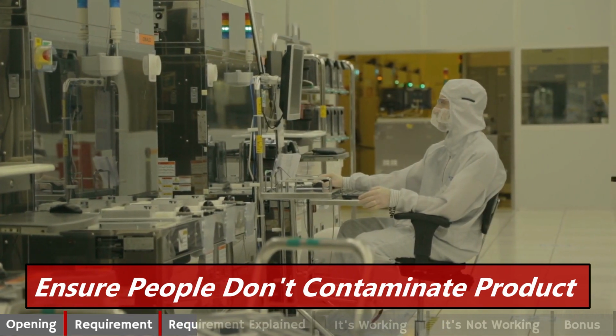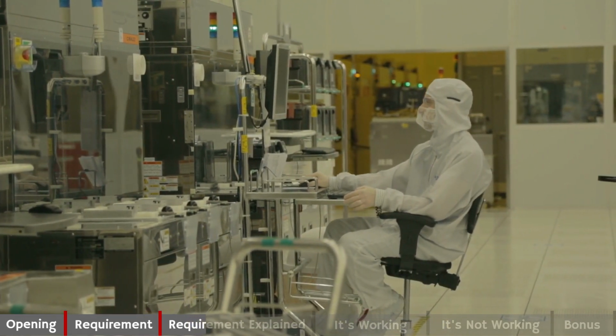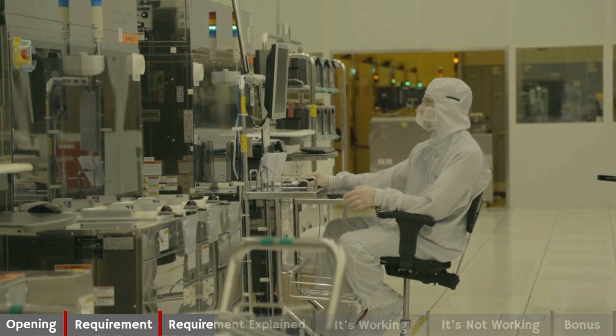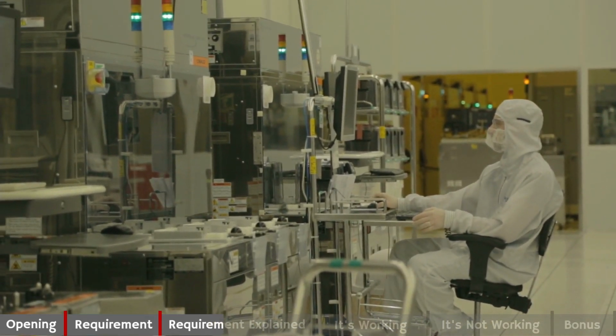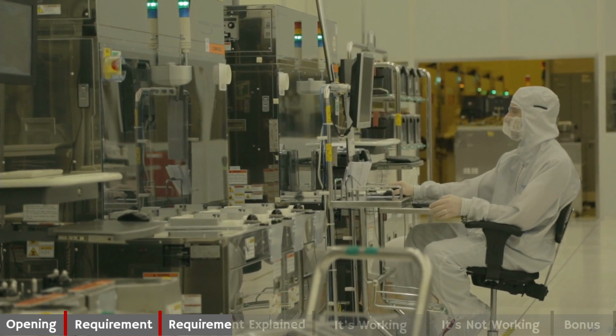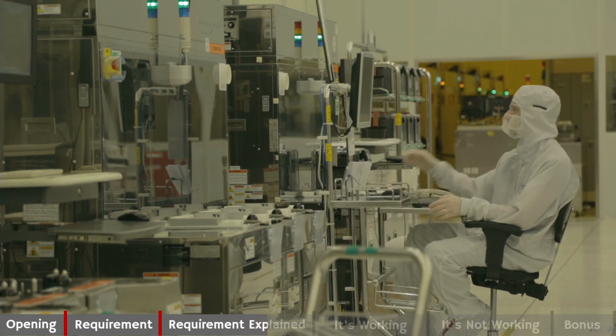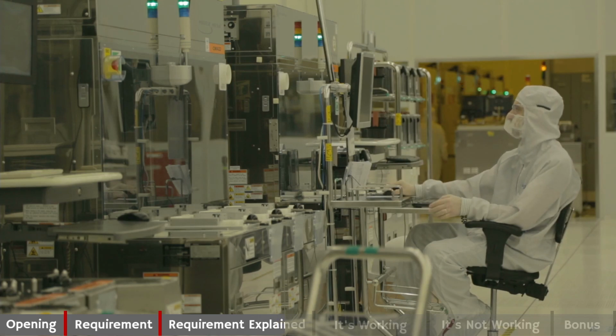We have to define the requirements for health, cleanliness, personal practices, and clothing related to the personnel that interact with our medical device. If people can contaminate our product, we have to control those points where that contamination could occur. Once we've defined those contamination controls, we have to establish and maintain procedures capturing those requirements. Personnel have to be trained on those requirements.